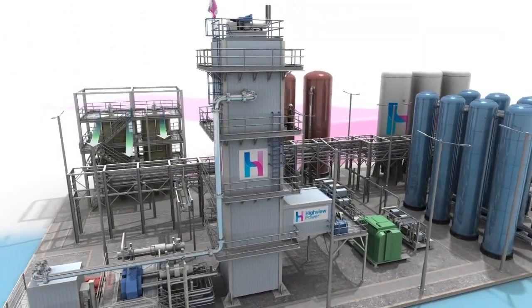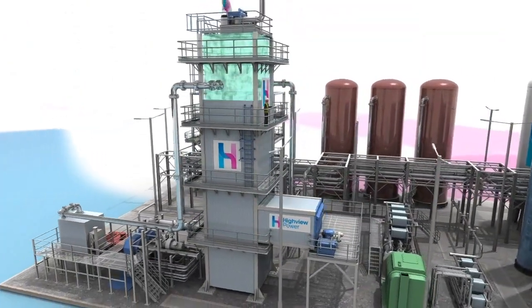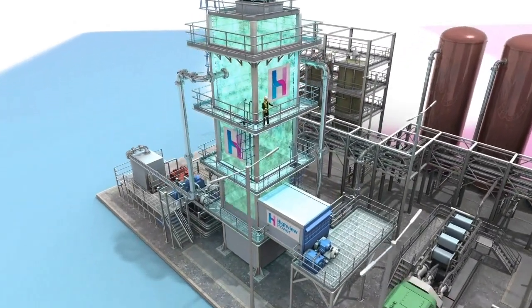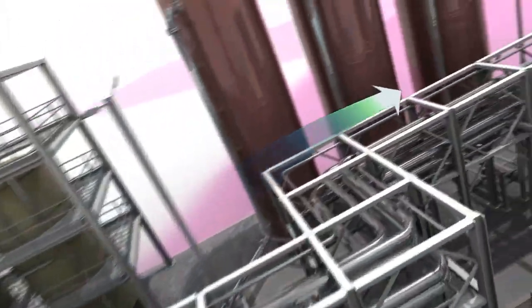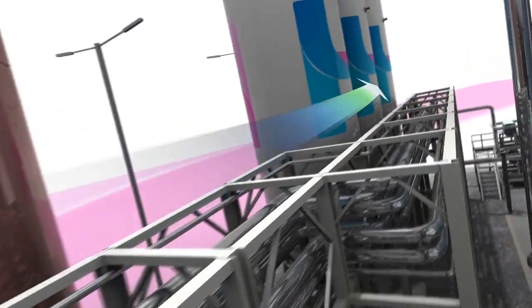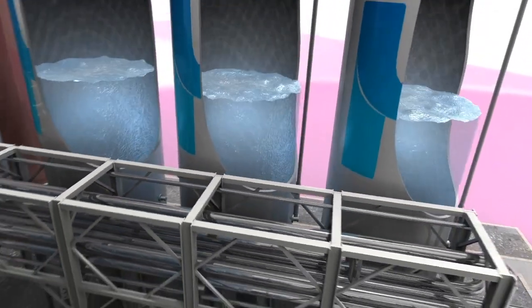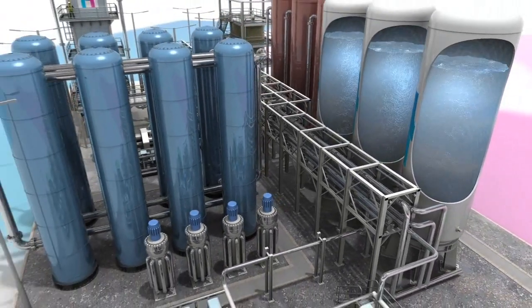Air is first cleaned and dried, and then refrigerated through a series of compression and expansion stages until the air liquefies. This process is based on the Claude cycle, which is over 100 years old. The liquefied air is then stored in insulated tanks at low pressure. These tanks are readily available from the industrial gas industry or the very large-scale LNG sector.